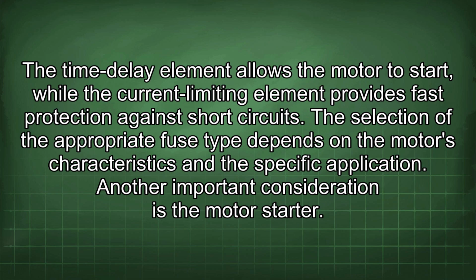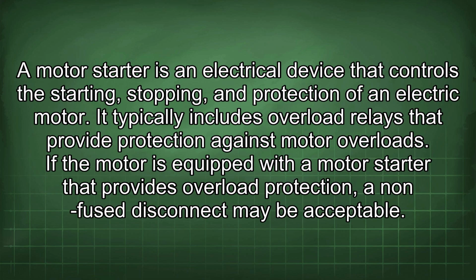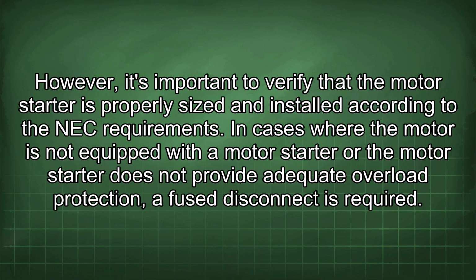Another important consideration is the motor starter. A motor starter is an electrical device that controls the starting, stopping, and protection of an electric motor. It typically includes overload relays that provide protection against motor overloads. If the motor is equipped with a motor starter that provides overload protection, a non-fused disconnect may be acceptable. However, it's important to verify that the motor starter is properly sized and installed according to the NEC requirements. In cases where the motor is not equipped with a motor starter or the motor starter does not provide adequate overload protection, a fused disconnect is required.